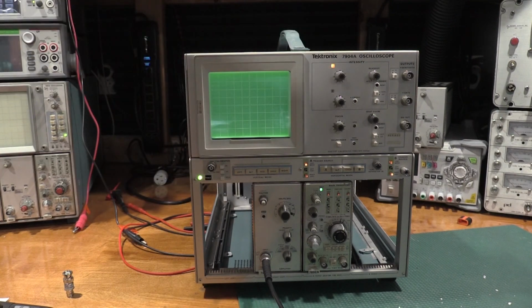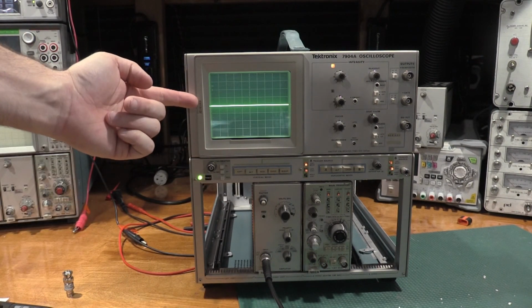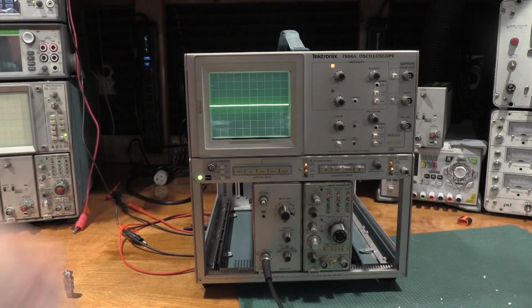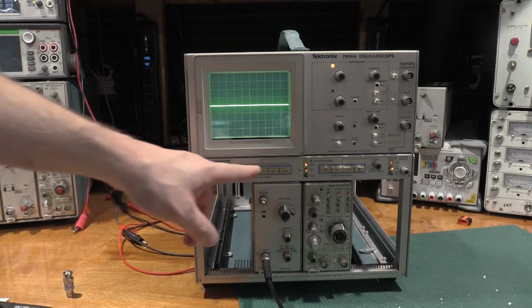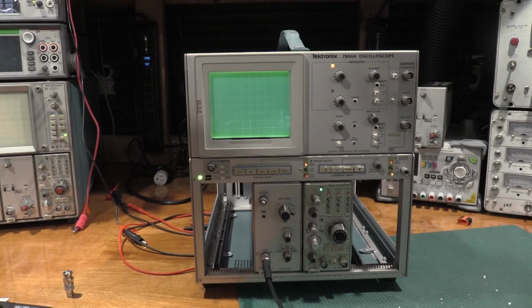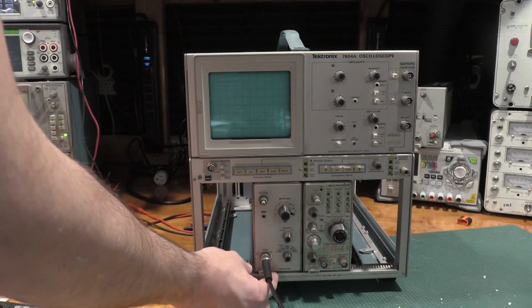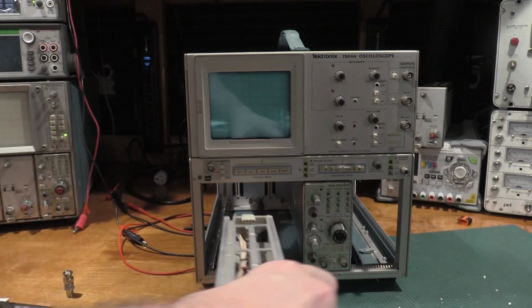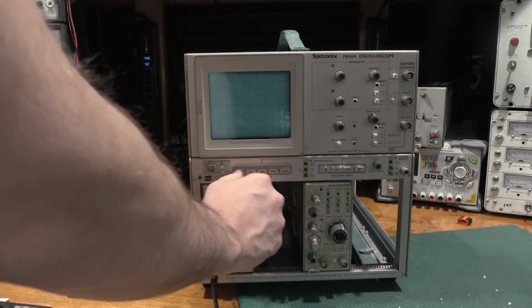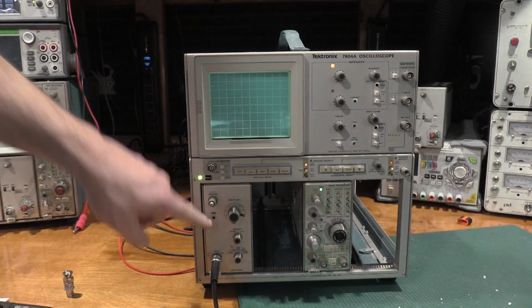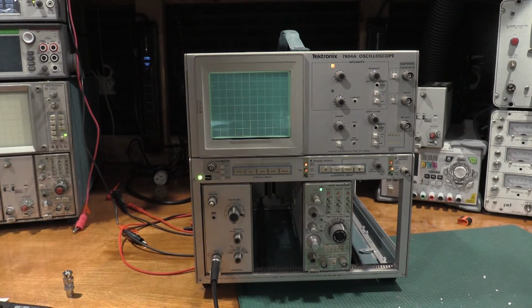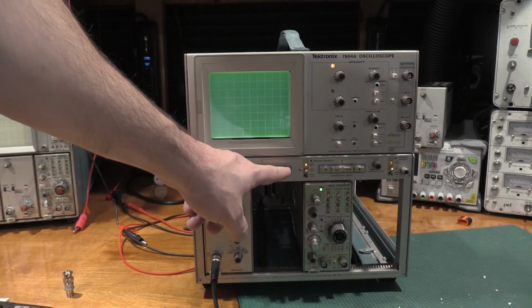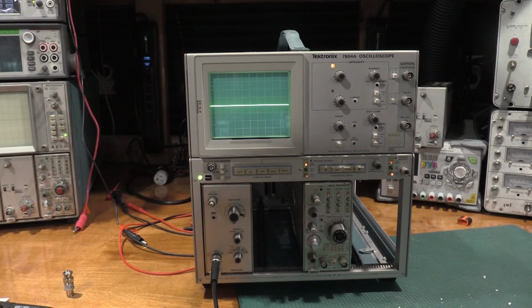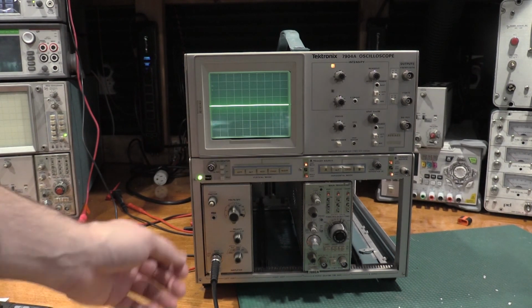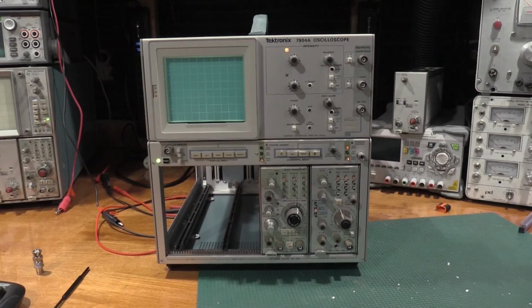Okay, we're checking channel isolation. So I have signal going in. We hit over to the left. We have no deflection, which is perfect. This is a 500 megahertz signal. And let's check the left port. Which is good because I only have one 500 megahertz amplifier, so I almost couldn't do this part. Check the right side. No deflection. Perfect. We have better than 80 to 1 isolation on the channels, as expected. Okay, all the vertical modes work as expected.